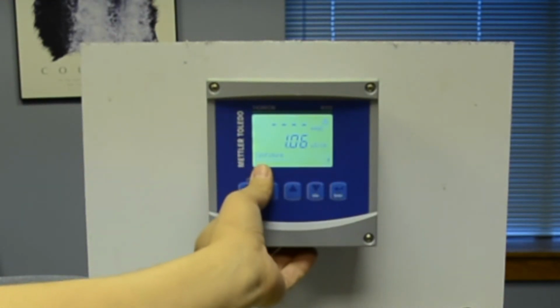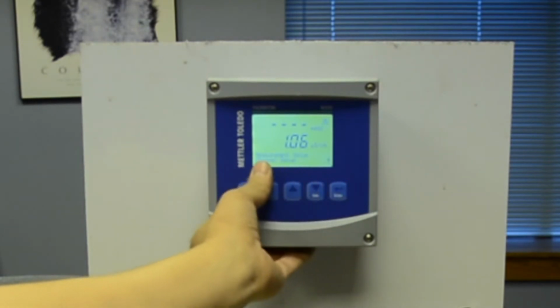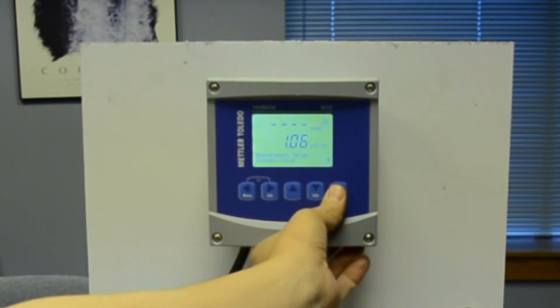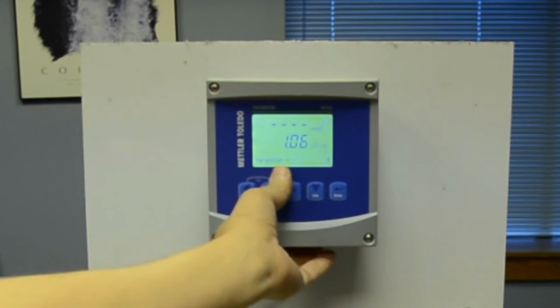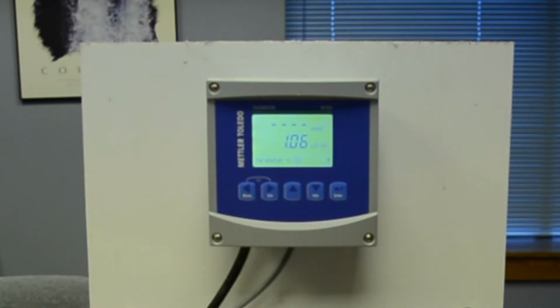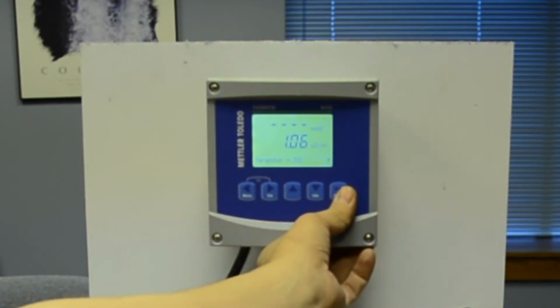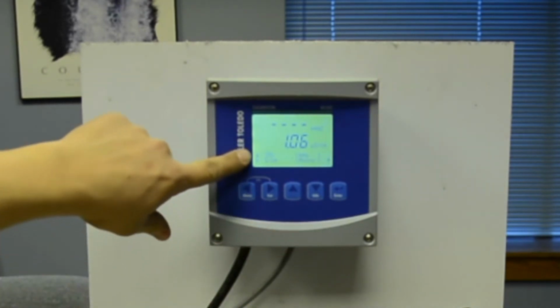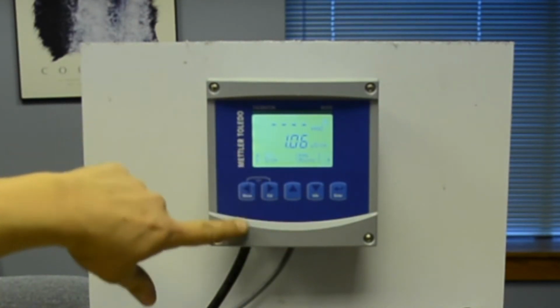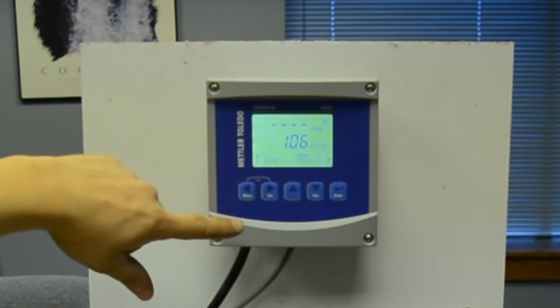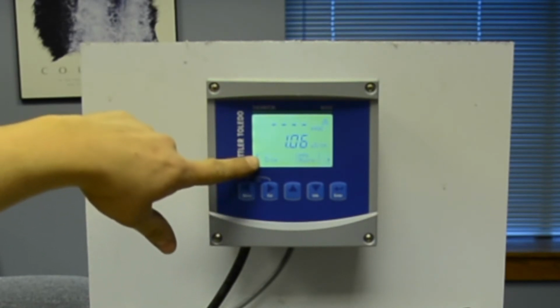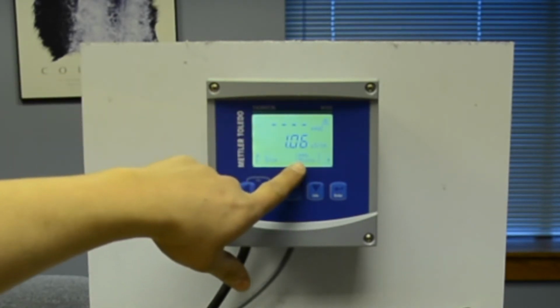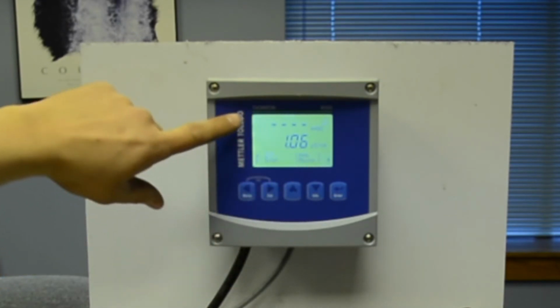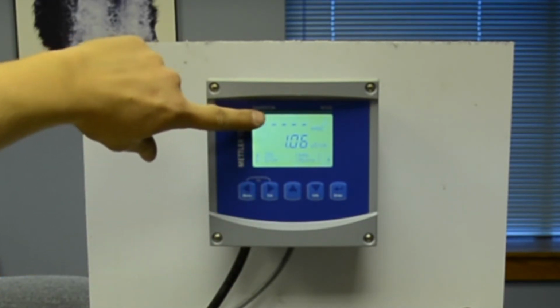Hit enter, then it'll say measurement, hit enter, then it says channel setup, hit enter again, and then parameter. The parameter is TOC because the sensor is located within the TOC unit. Hit enter again, and now it will give you different channels. You see A, B, and then as we continue down you would see C and D. Right now channel A is set up for TOC. That's reading it in parts per billion, and that's your channel A located here on the top.